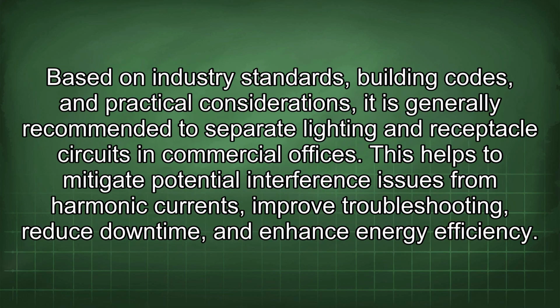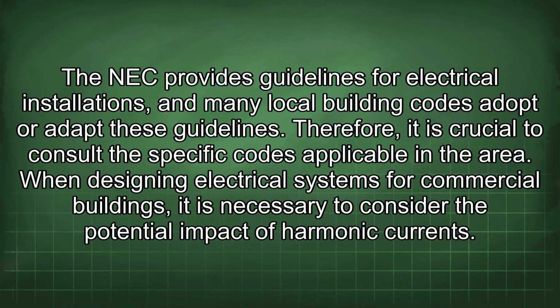Based on industry standards, building codes, and practical considerations, it is generally recommended to separate lighting and receptacle circuits in commercial offices. This helps to mitigate potential interference issues from harmonic currents, improve troubleshooting, reduce downtime, and enhance energy efficiency. The NEC provides guidelines for electrical installations, and many local building codes adopt or adapt these guidelines. Therefore, it is crucial to consult the specific codes applicable in the area.